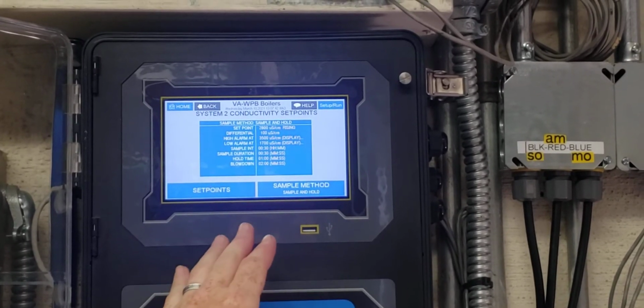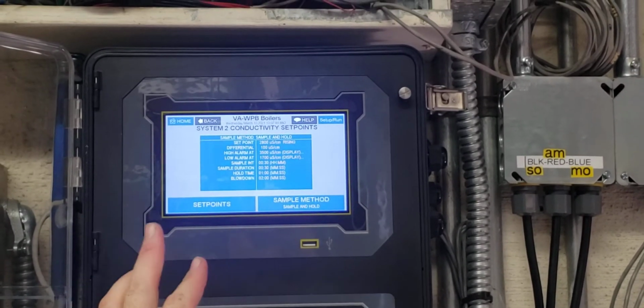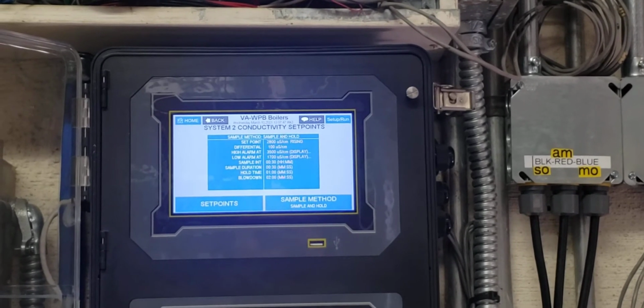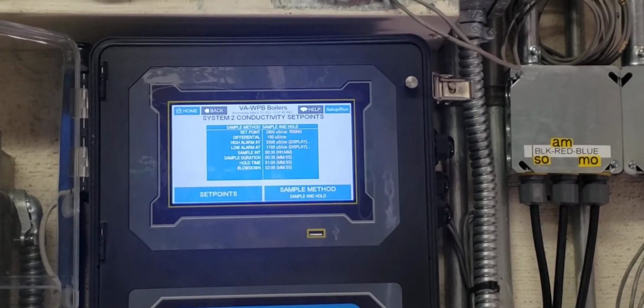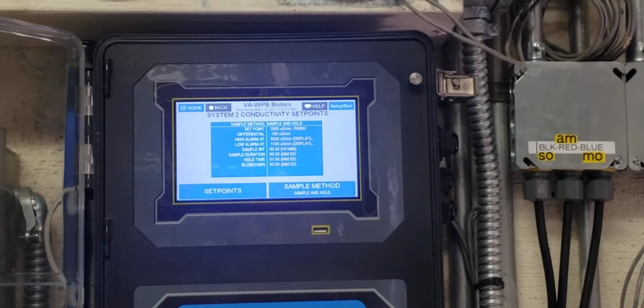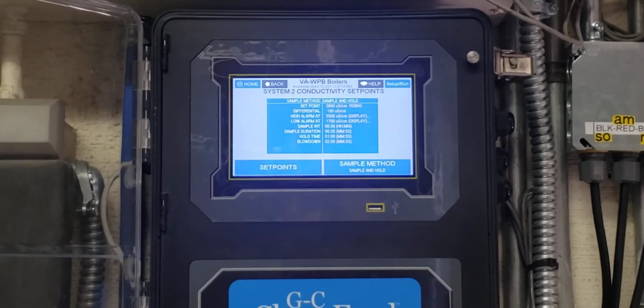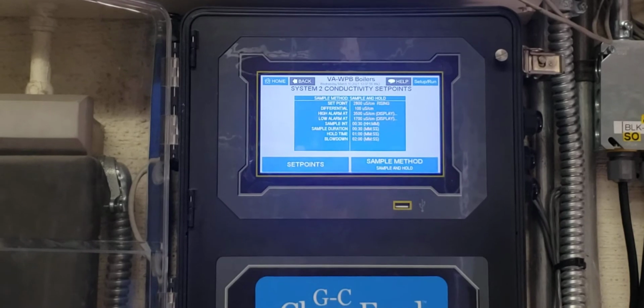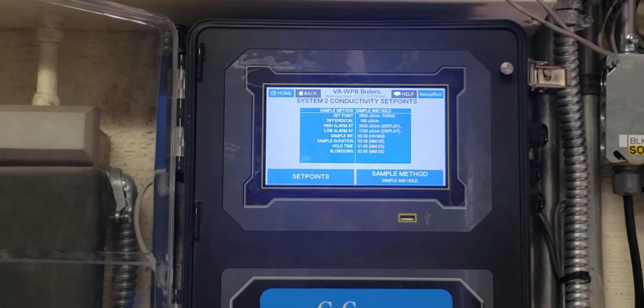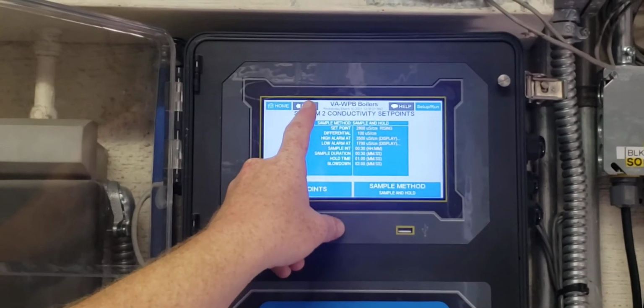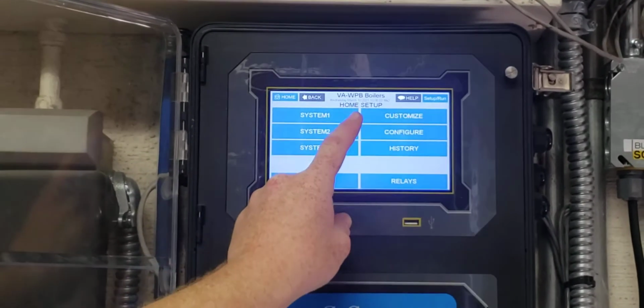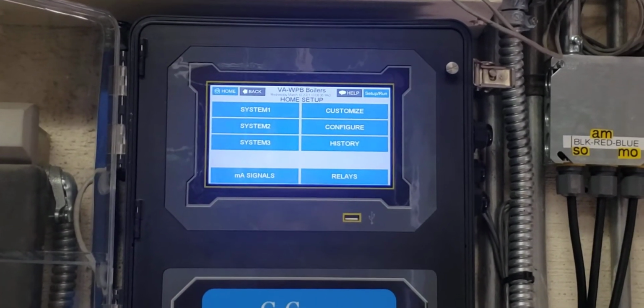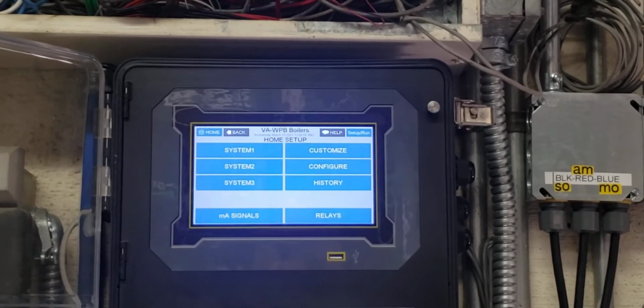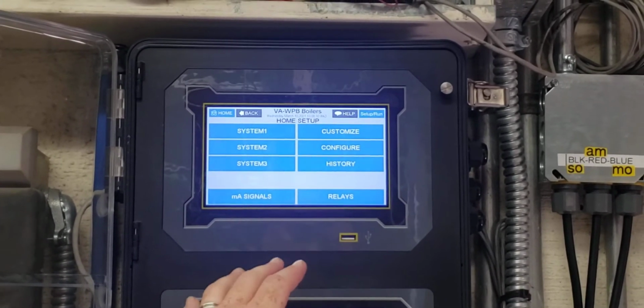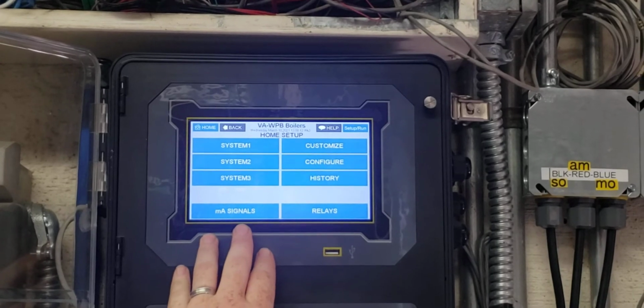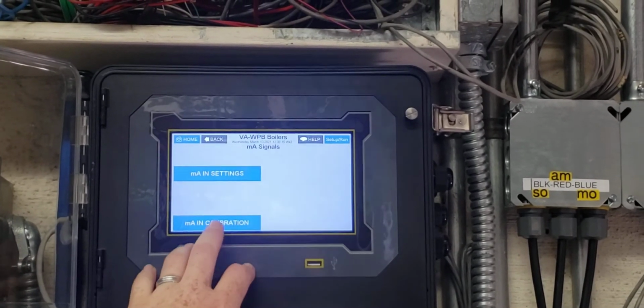Okay, so the question is, do we want to go with these settings, or do we want to go with the 15-minute settings? I might just still play it by ear. Boiler 2 is down again and won't be on again, so we won't be able to check this scenario again. Right now we're manually blowing down because that actuator keeps getting hung up. So technically, all this is hearsay until we get these actuators. And the main point of the video too is just so the guys know what's going on in the milliamp signals.